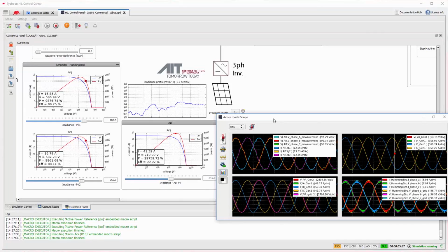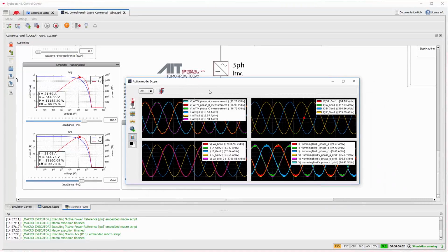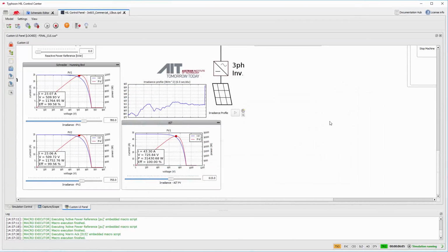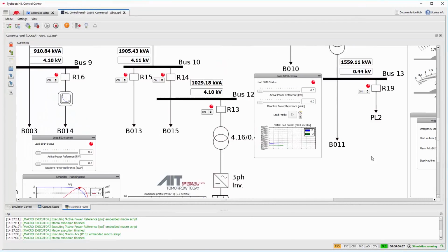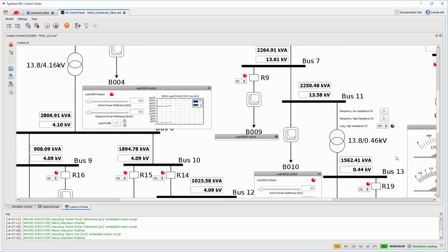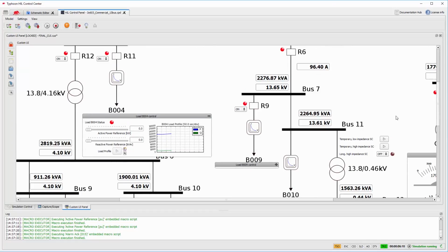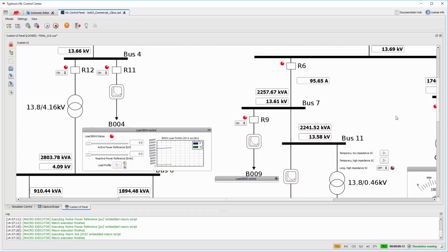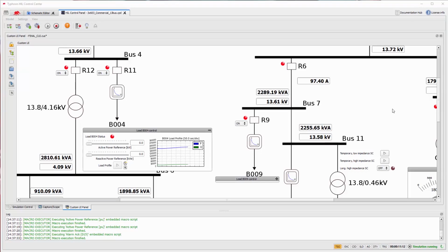Different scenarios can be studied according to what the user desires. Changes in power reference, irradiation, contactor control, and device faults are only a few examples of what can be done in real time. In this video, two scenarios will be studied. In the first, we will cause short circuits and analyze the system response. In the second, we will check how our controllers behave under a low voltage ride-through test.